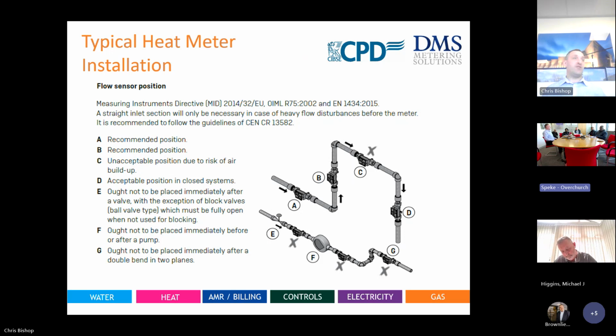So, typical heat meter installations. Yet again, there's a visual on screen, but I'll just go through the relevant points. We always state, and push, that the heat meters are installed on the return part of your system. Very important. The purpose of that is the return is the lower temperature. There's generally fewer devices on the return. The pumps are generally designed on the flow. A lot of other devices are generally supplied on the flow.